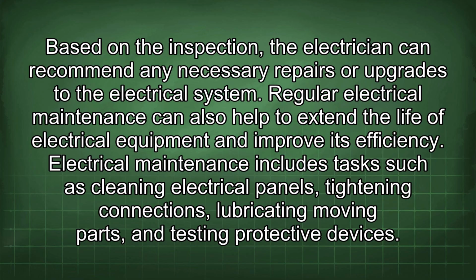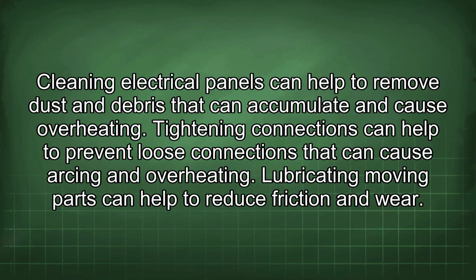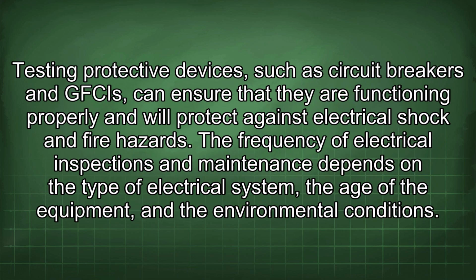Electrical maintenance includes tasks such as cleaning electrical panels, tightening connections, lubricating moving parts, and testing protective devices. Cleaning electrical panels can help to remove dust and debris that can accumulate and cause overheating. Tightening connections can help to prevent loose connections that can cause arcing and overheating. Lubricating moving parts can help to reduce friction and wear. Testing protective devices such as circuit breakers and GFCIs can ensure that they are functioning properly and will protect against electrical shock and fire hazards.